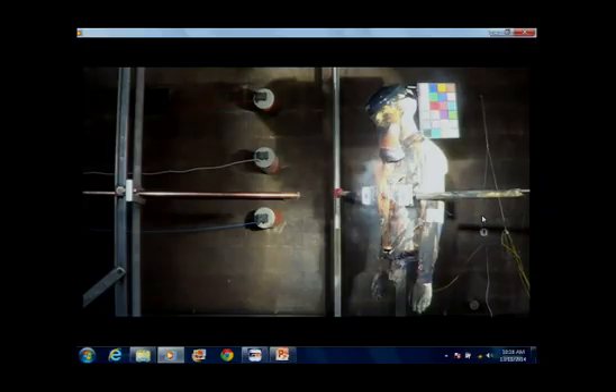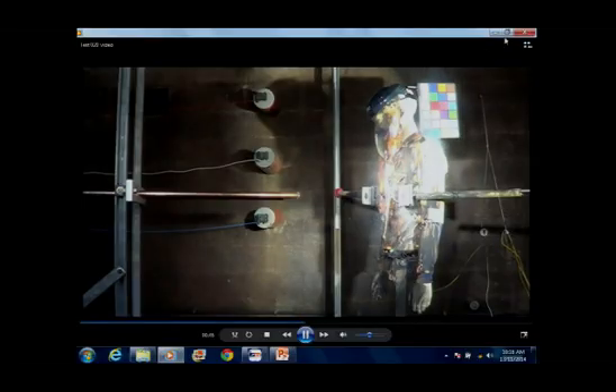It's totally destroyed. There is so much more energy in burning clothing than what there is in the arc. So up until the point that our cotton clothing ignites, it provides protection. Once it ignites, it makes the injury worse by increasing the depth of the burn and the area of the body that's burnt. Let's compare that with arc-rated clothing.